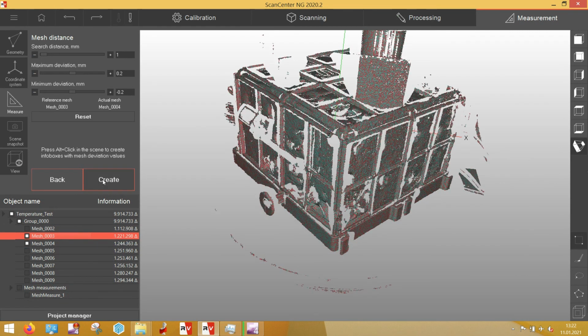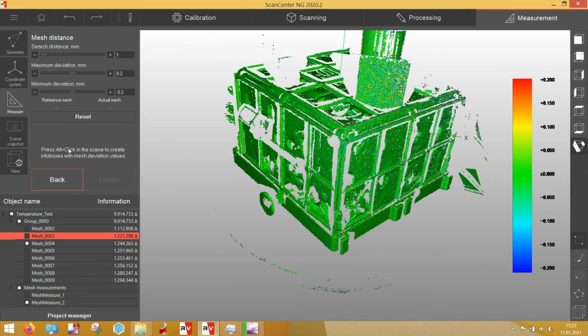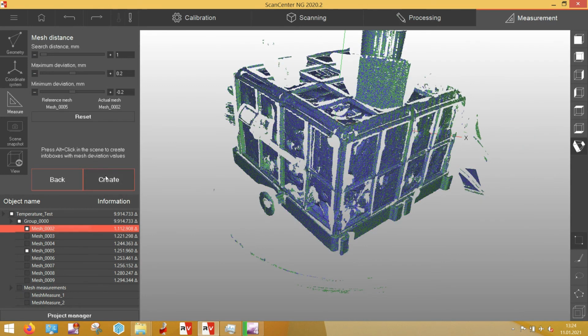So in this case, I'm, let's say, comparing the scans in several steps, and the first scan that you have here on the list of the scans is always the cold scan before any kind of heating up, and after that come the time steps, 10 minutes and so on, like I explained before. So the first comparison is between the scanner in cold condition and after 10 minutes heating up. You will see that it really looks good. Then the second comparison that you will see is between 20 and 10 minutes as well.